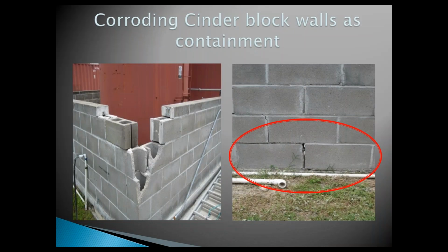Cinder blocks. It's very difficult to maintain cinder blocks for containment, and they also should be sealed properly such that they are sufficiently impervious, and they're subject to cracking and things like that. So they're not the best containment in the world.